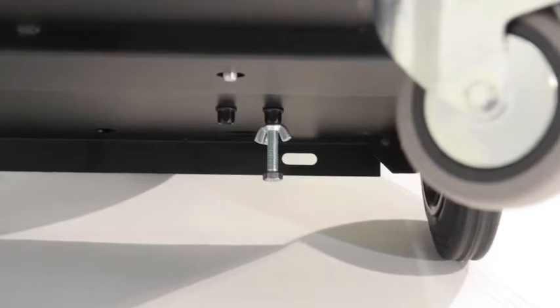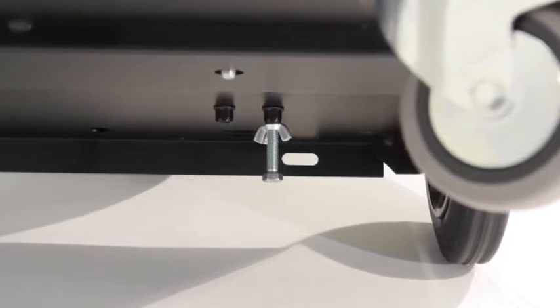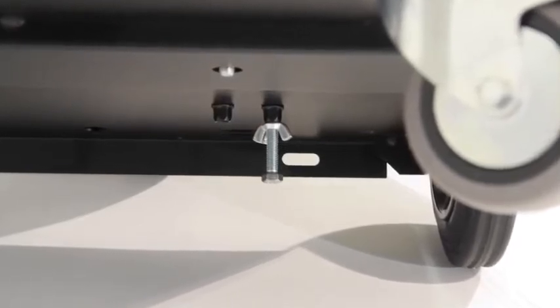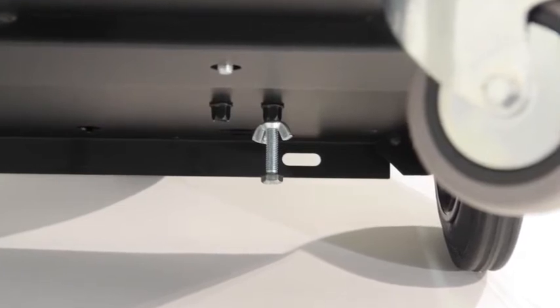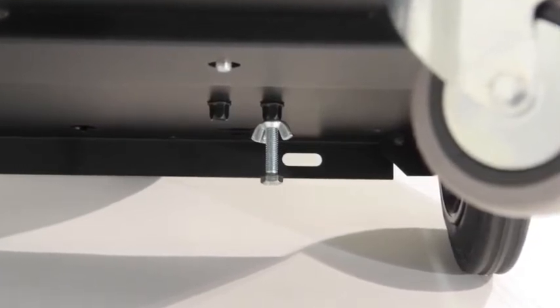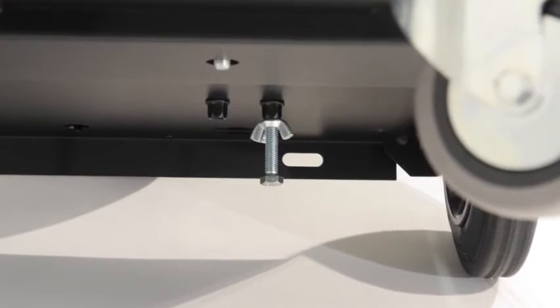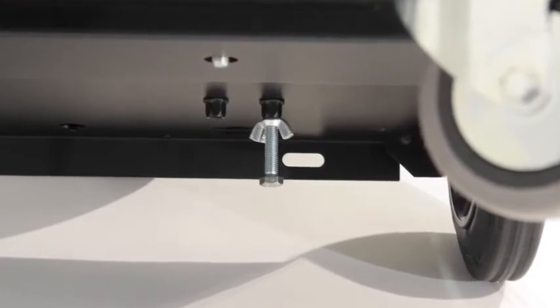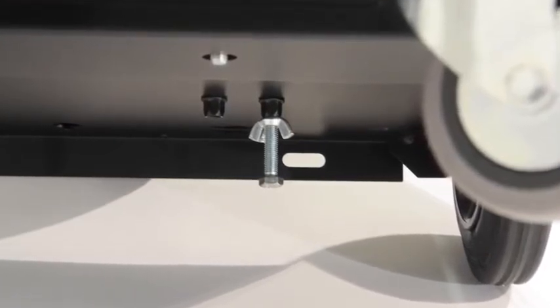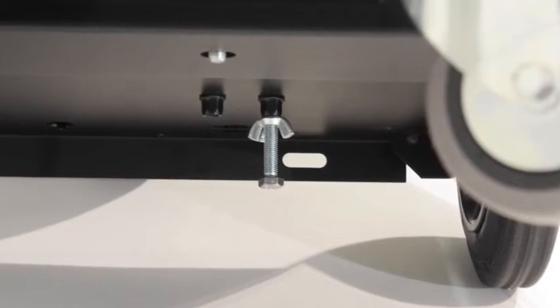Removing the refrigerant load cell set screw, you'll find a bolt with a wing nut on the bottom of the machine. All you need to do is loosen the wing nut and remove the bolt, and that will free up the load cell for the commissioning of the machine.